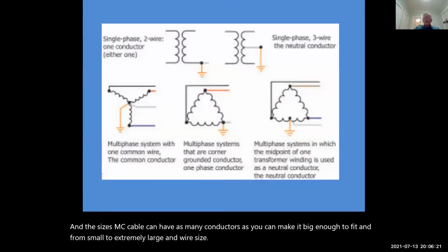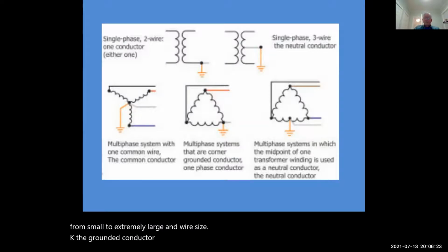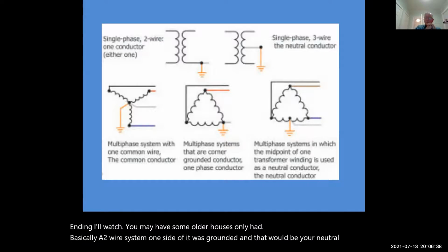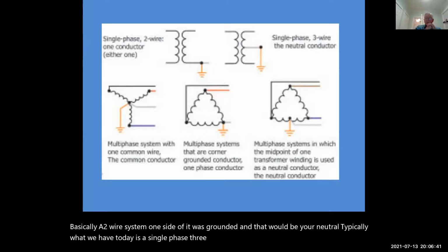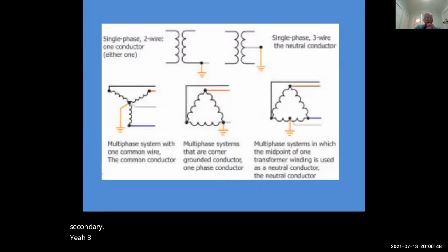Okay, the grounded conductor or neutral, depending on what you may have: some older houses only had basically a 2-wire system. One side of it was grounded, and that would be your neutral. Typically, what we have today is a single phase, 3-wire system. The neutral ties to the midpoint of the secondary. With 3 phases, you're going to have a Y system where the common point will be grounded, and that's again the neutral.